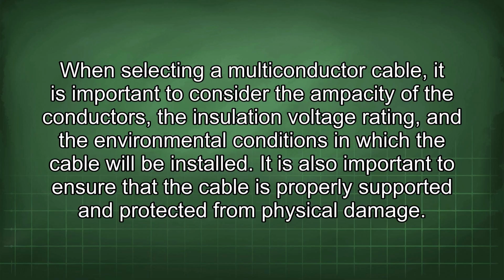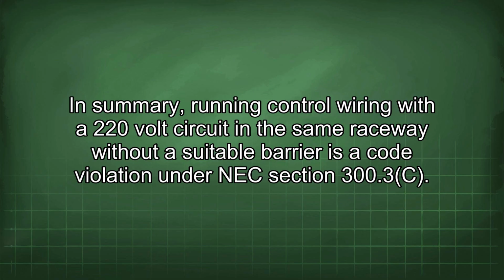It is also important to ensure that the cable is properly supported and protected from physical damage. In summary, running control wiring with a 220-volt circuit in the same raceway without a suitable barrier is a code violation under NEC section 300.3c.